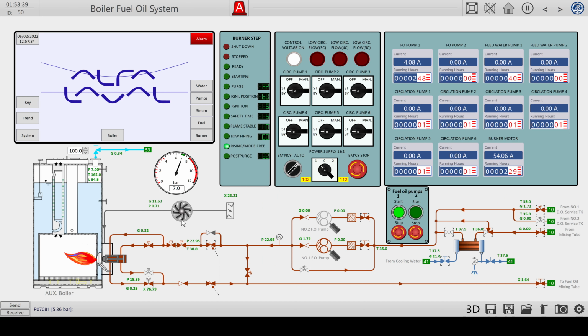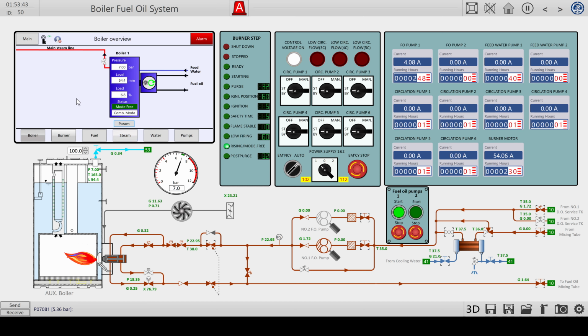So here we are in the boiler section. Only the auxiliary boiler is running, as we don't have the main engines running to use the exhaust gas. We are using the first service tank with diesel oil, as said before, firing the first fuel pump, and we have a steady flame and a pressure of 7 bar.